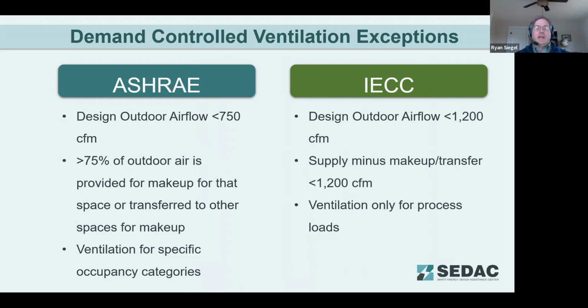And when you're getting into demand controlled ventilation, so here we're looking at inside buildings rather than parking garages where we were before. So if we've got ASHRAE, we see here the design airflow is set much lower at 750 CFM versus IECC. The threshold is 1200 CFM before you trigger DCV.